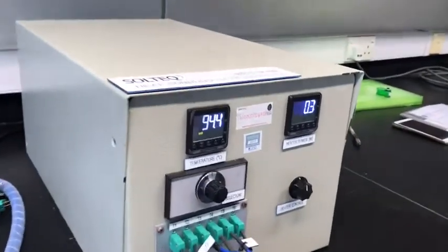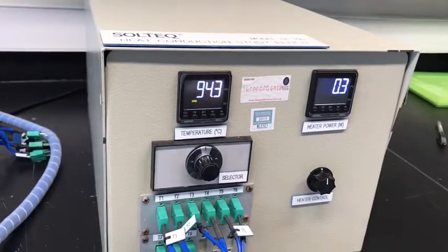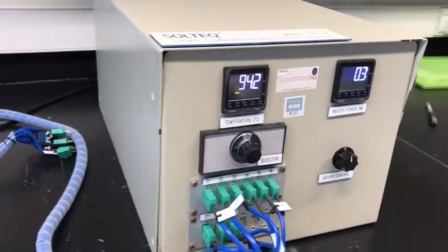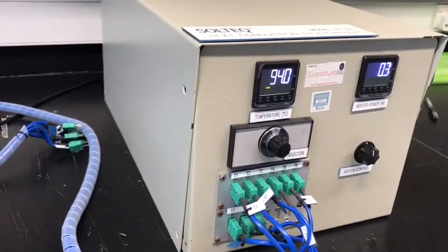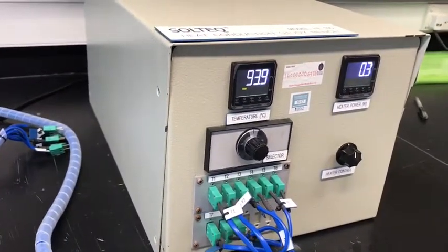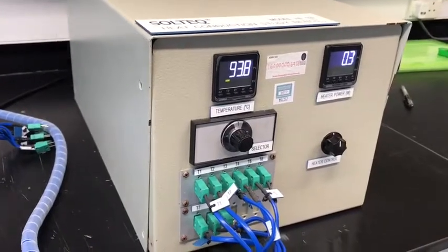Temperature along the linear module should start to increase after a few minutes. And the last one, make sure that the temperature reading decreases to the water cool temperature for the entire temperature sensor.